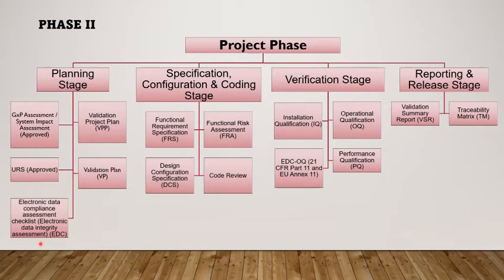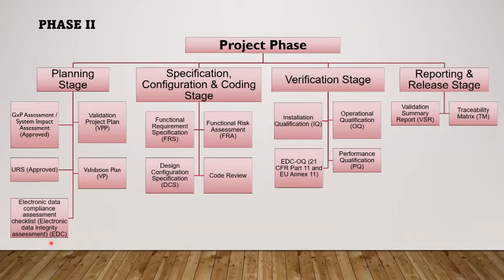Next is the electronic data compliance assessment checklist, which is prepared to verify that the system is in compliance with 21 CFR Part 11 regulation. If any gap is identified in this checklist, it can be discussed with the vendor for system control or procedural control.